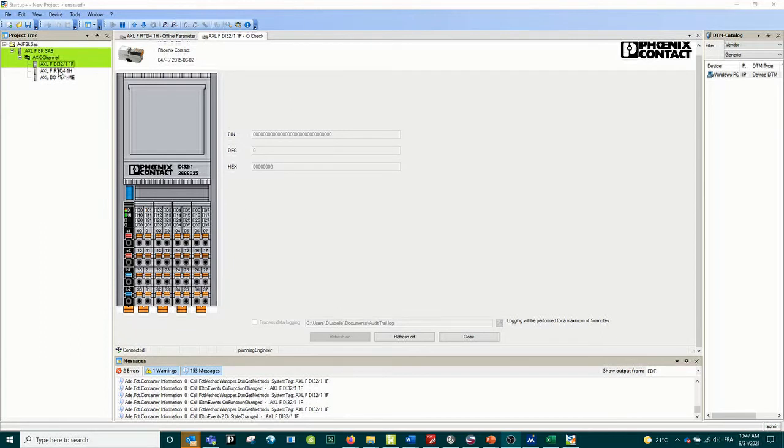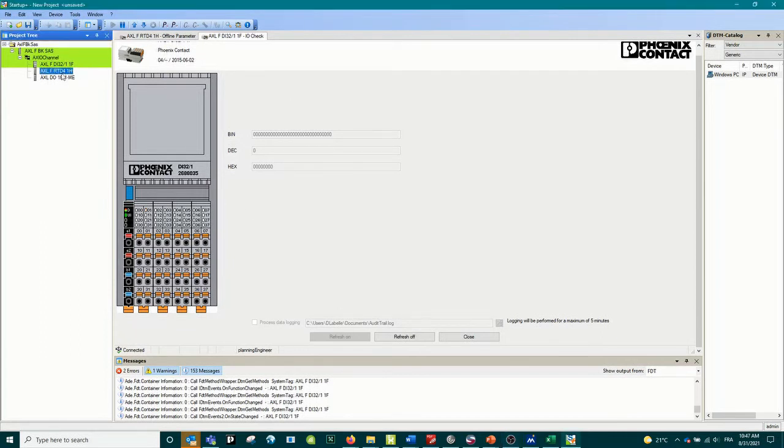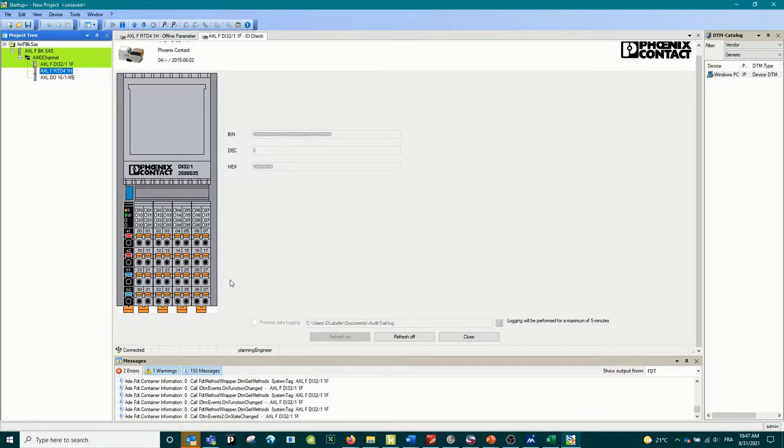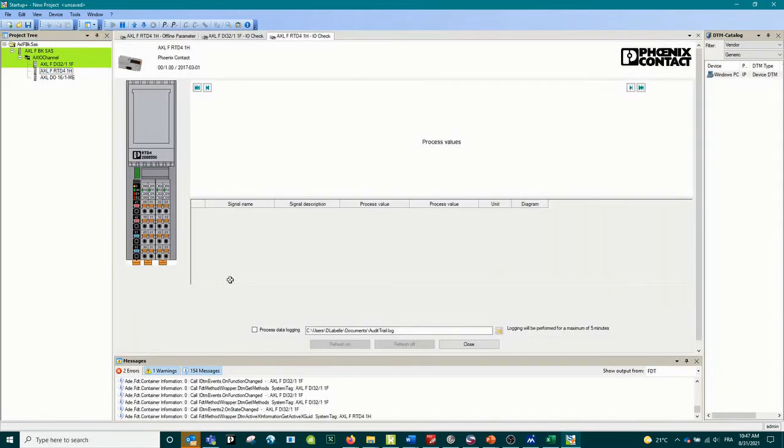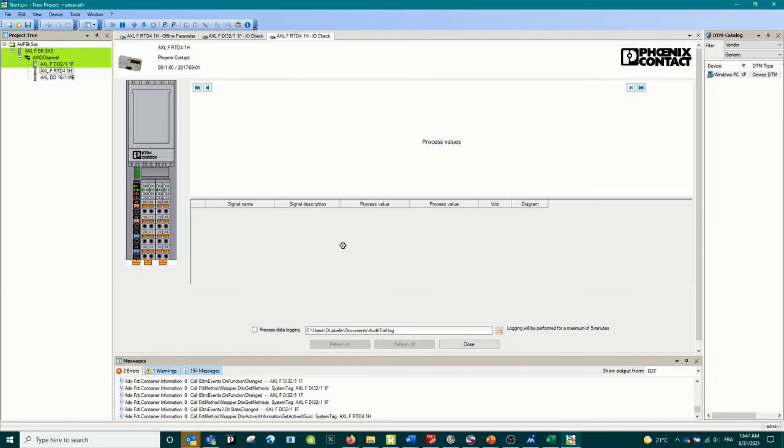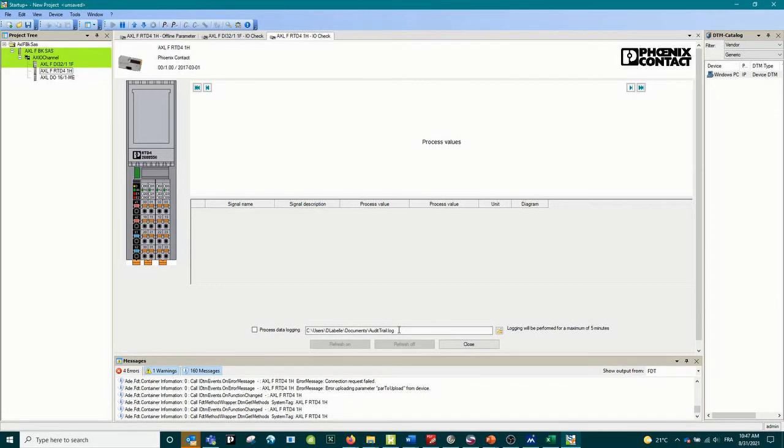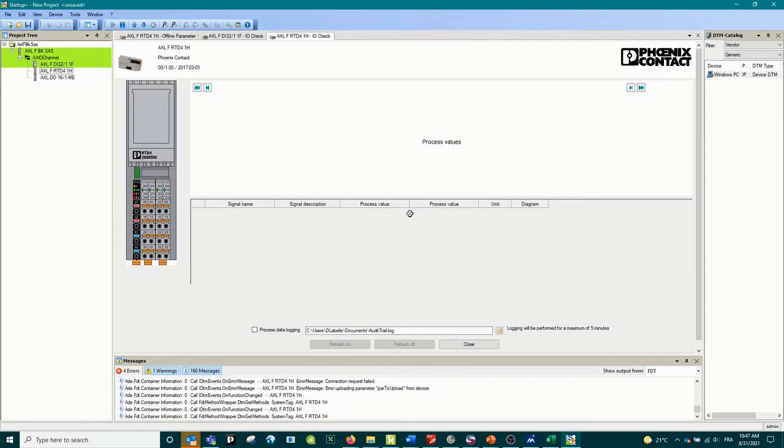We will do the exact same thing using the RTD card, so function IO check. For everything that is analog it's going to be a little bit different because it's going to show you a graphic, so you can see the value directly on a graphic. You can log everything into a text file so you can follow for a maximum of five minutes what is going on. If you need to activate the level of something or the temperature you will see right away what it looks like and what kind of data will be sent directly to the PLC.